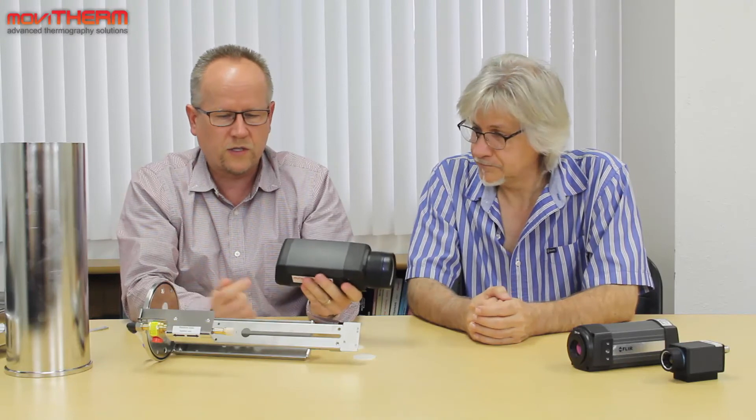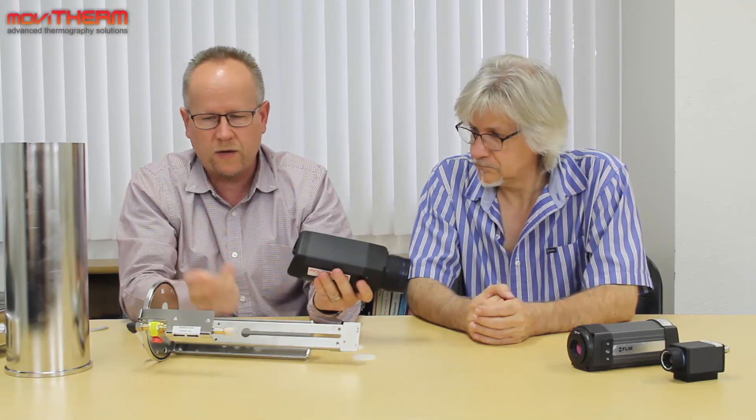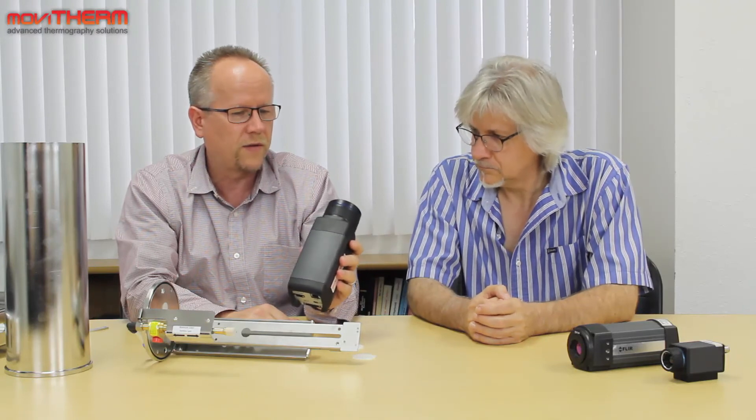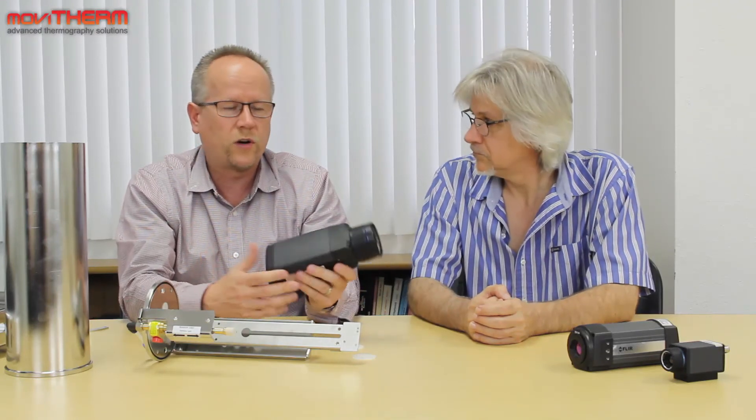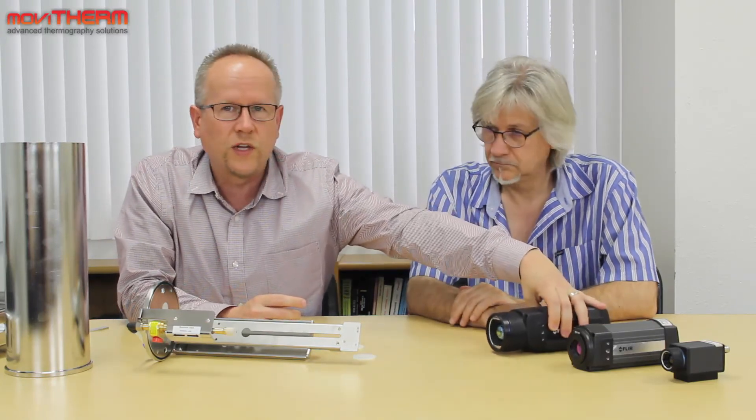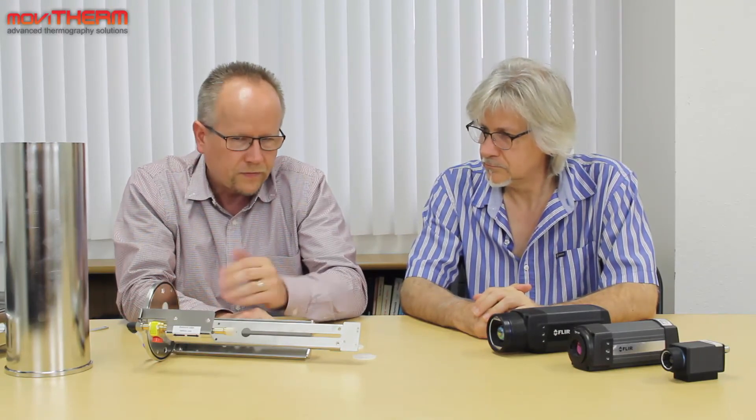Then I just plug in my ethernet cable, my power cable, and for a simple installation that's pretty much all I need. If you have a situation where you have an outdoor installation where in the winter it gets very cold, there's no need to have the vortex cooling option running. You can put a thermostat in there and then basically turn the air supply off to the vortex tube in the winter if it's cold enough already and save a lot of money not blowing so much air through this.